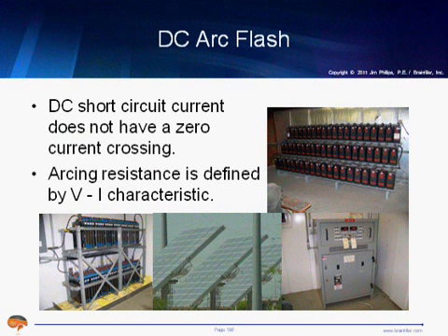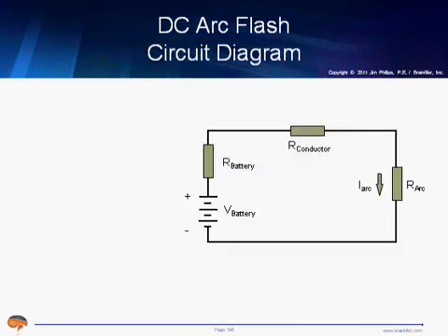And the basics of DC arc flash calculations, I actually talk about this in one of my training programs, but the basics is you have a circuit, and you look at the information of your source resistance and your conductor resistance, and those can be obtained. But the missing link is you also add the arc resistance. And the question is, well, where does that come from? Well, there's a series of equations that you can use with an iterative solution. And once you know what the arc resistance is, then you can revert back to some of the basic power equations. You know the arcing current, you can calculate that. Once you know the arcing current, I squared R, that's the power in the arc. And once you know the power in the arc, factor in time. That gives you the energy in the arc.